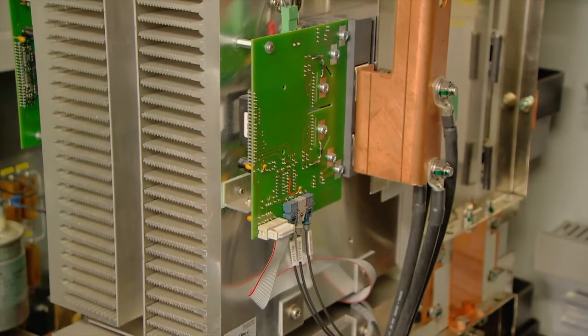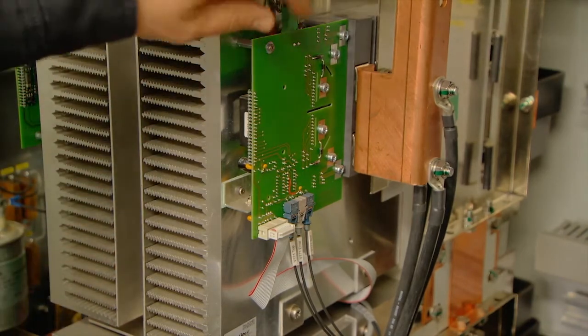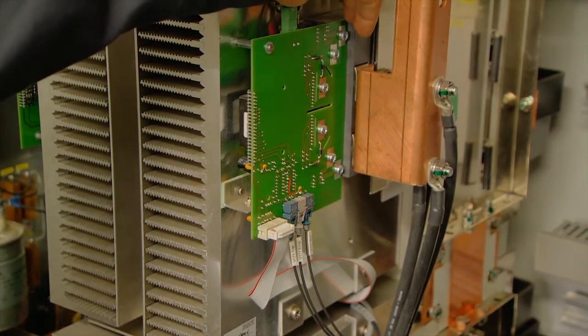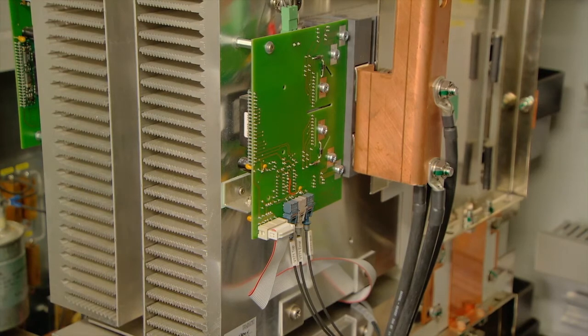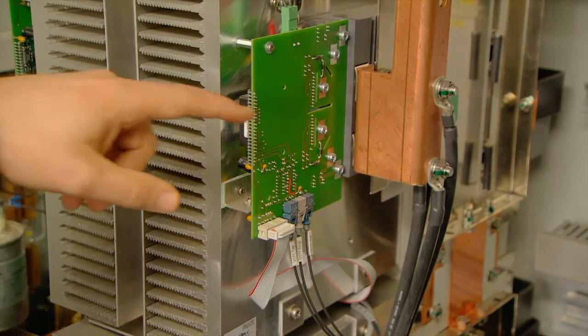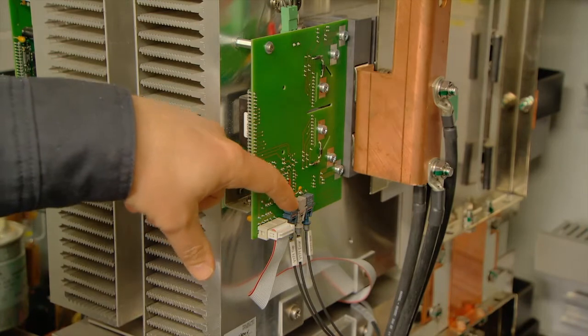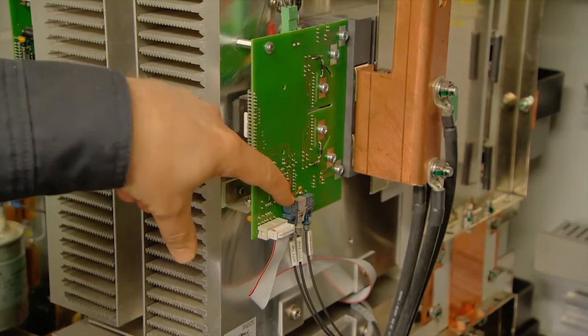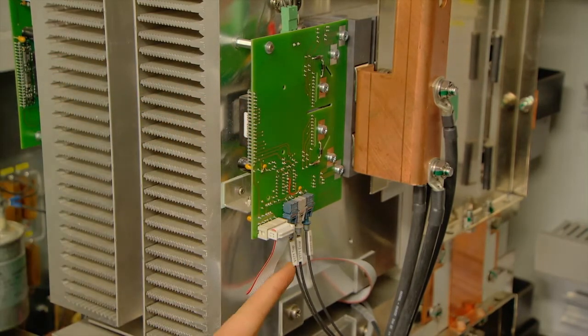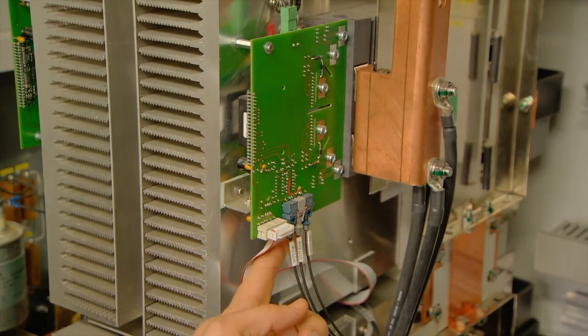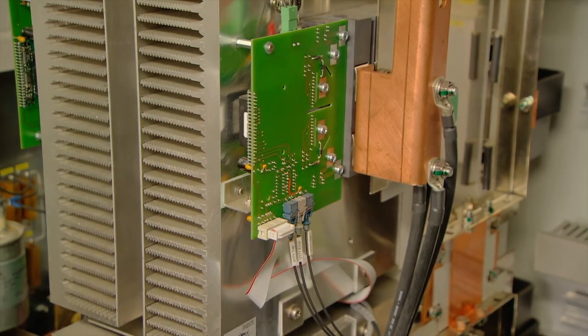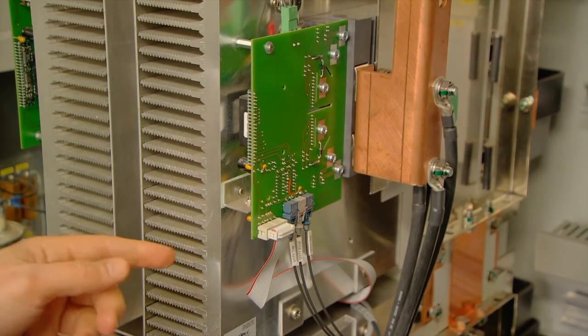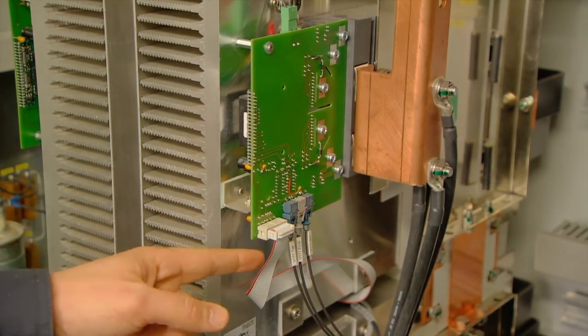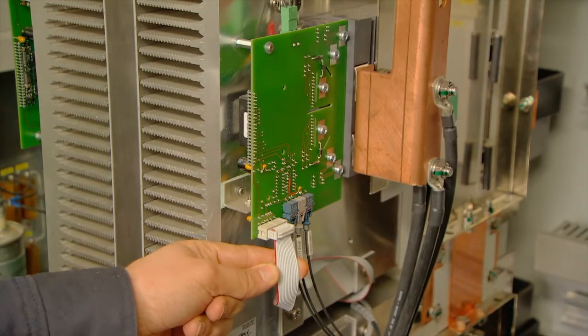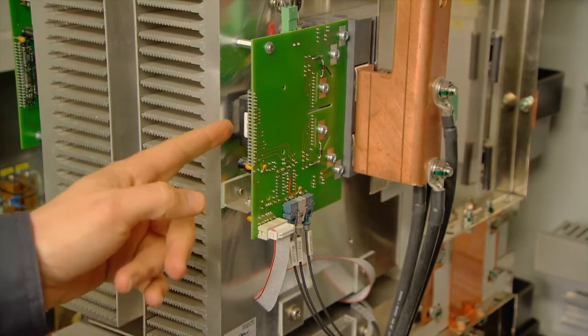The entire converter has 6 IGBTs. Each IGBT is built up by a control board and the IGBT itself. Firing the IGBT is controlled over an optical link. The optical link has 2 firing signals at the outer and a return signal for error at the middle. There is a second signal for the control board, and that is in this flat cable, and that's mainly controlling the temperature of the IGBT.